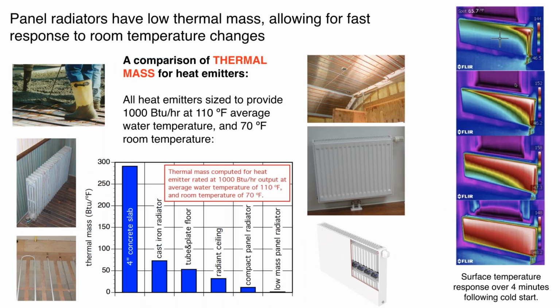There's really very little water in one of these panels. There might be a pint of water in a radiator this size, and that allows the panel to respond very quickly. So if you're bringing a room out of setback, this sequence of images over here on the right shows you this is when the water is first starting to go into that panel, and then this is 4 minutes later. And that panel is starting to approach a steady state condition.